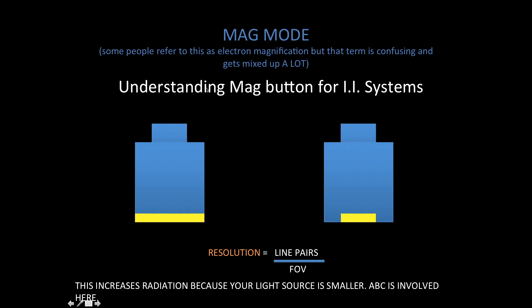The size will correspond more to a one-to-one ratio, therefore you don't have the minification that happens as part of our normal process, in which you go from a bigger surface area to a smaller surface area. The resolution formula is line pairs over field of view. You can see why magnification not only magnifies your image — since you're displaying a smaller anatomical surface on a bigger screen, your entire screen will be occupied by this smaller anatomic section — but also you have an increase in resolution by decreasing the field of view. That is something very specific to image intensifying tubes.